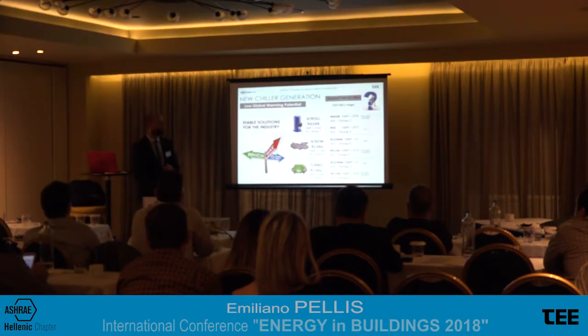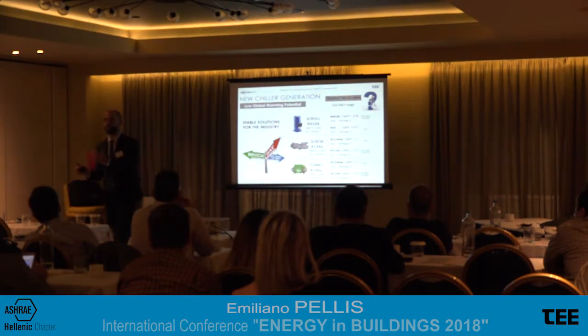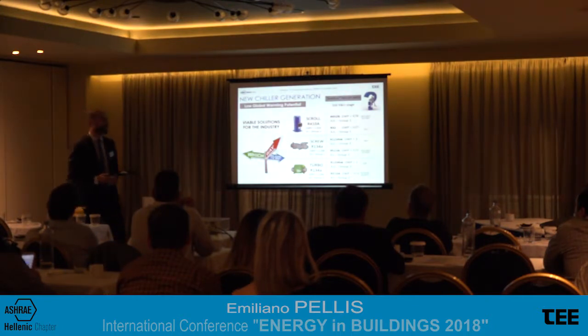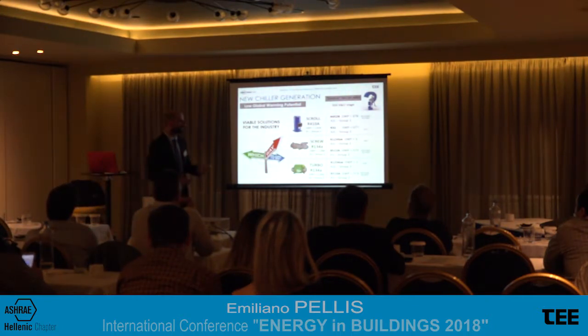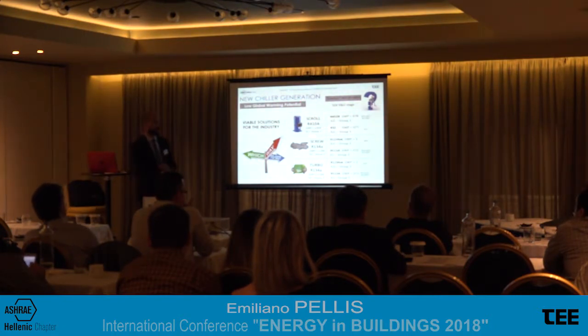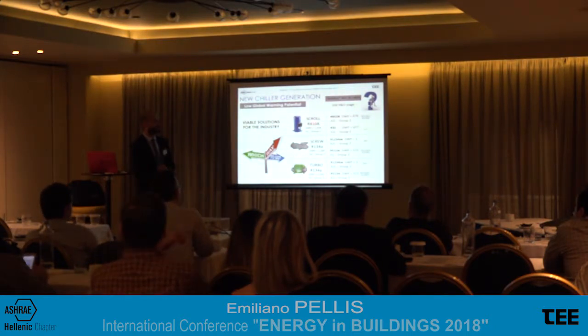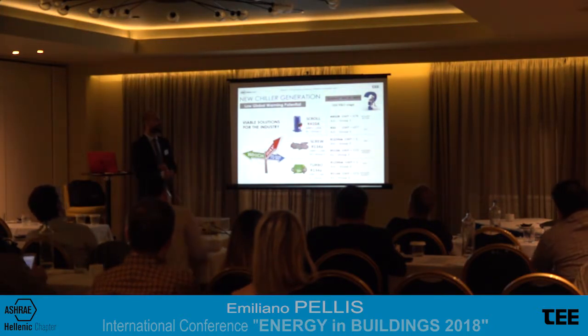On the other side, the 513A represents almost a drop-in solution. It's not that easy, but it's very similar. We have just to refill the unit. What we need is only to verify some points related, for example, to the material compatibility, so the oil, the gasket of the compressor, and so on. What about the scroll? Here the situation is more critical for the market. Today the dominant solution is 410A.